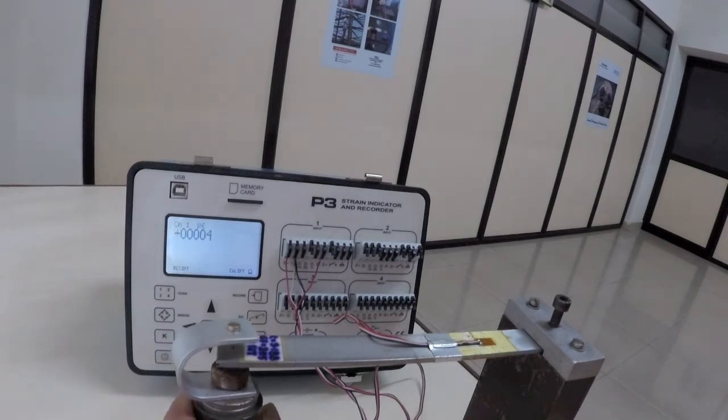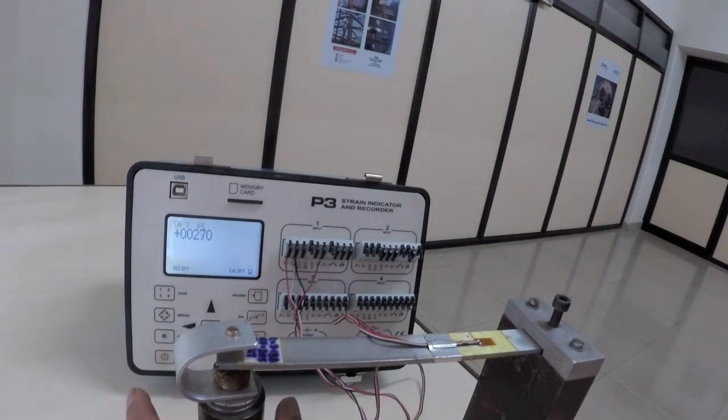This does not mean that the strain on the beam is doubled. It means that the Wheatstone bridge is giving double the output from the same strain because of the half bridge configuration.